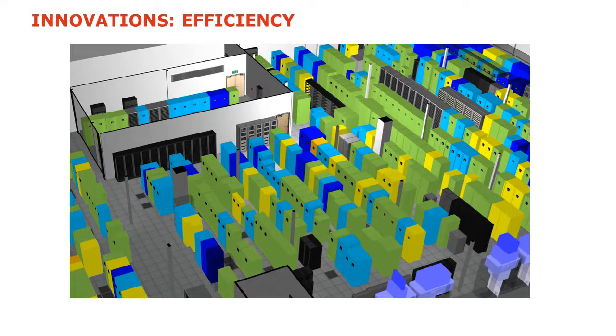And the challenge we face in the data center, a little bit different to buildings that are designed for people, is that the deployment of IT equipment across the floor is not homogeneous. There are areas of high density energy consumption, and there are areas of low density. So getting the airflow correct, getting the supply correct, getting the heat extraction correct is quite a complicated business. And managing the airflow does require intelligence and a degree of prediction. So increasingly what we're seeing, to Steve's point, is tools that assimilate the data, collect the data, process it, and then apply a set of logic, a set of rules to that data and determine the best way to manage what is actually a very complex environment, one that's becoming too complex for humans to manage themselves.